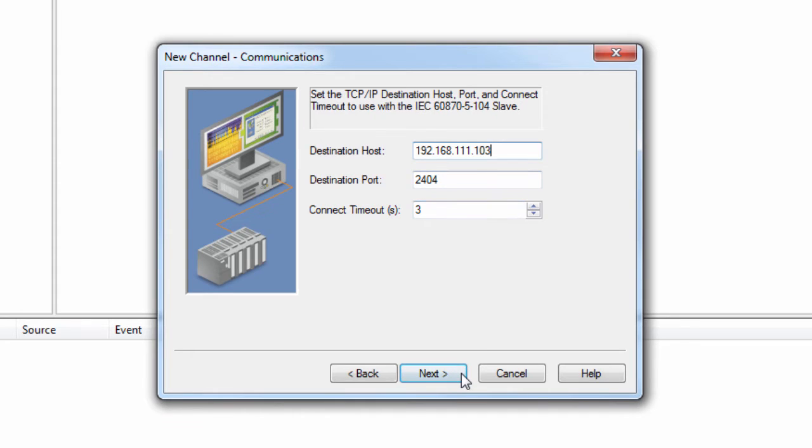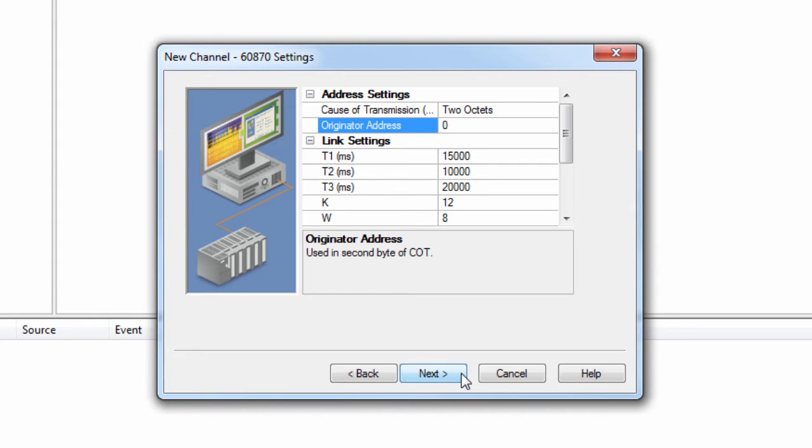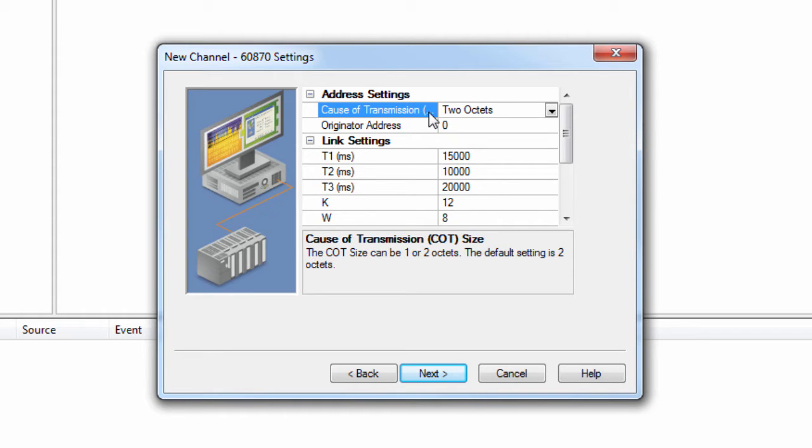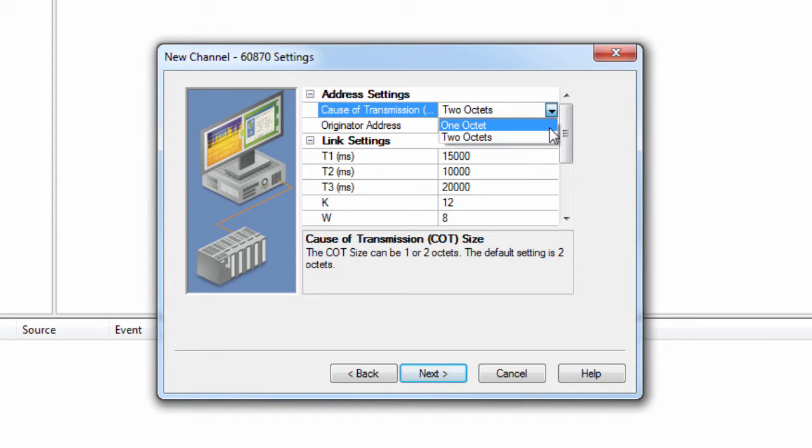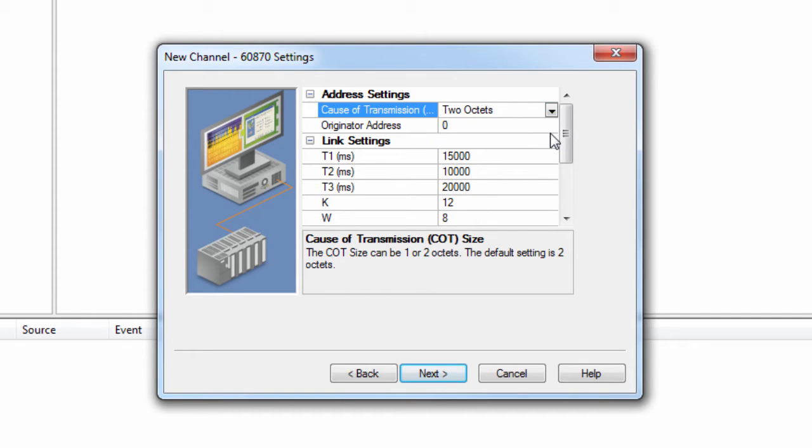Click Next to review the final settings for the channel. The Cause of Transmission Size specifies whether or not the master's originator address will be included in the messages to the IEC device. When two octets is selected, the originator address is included. And when one octet is selected, the originator address is not. The default setting is two octets.